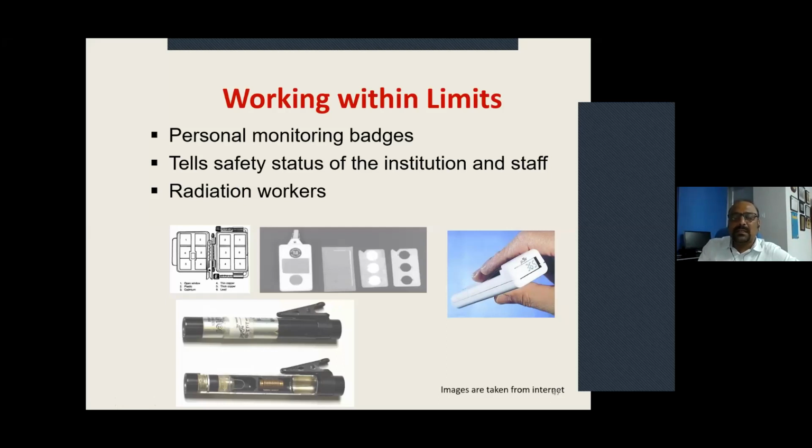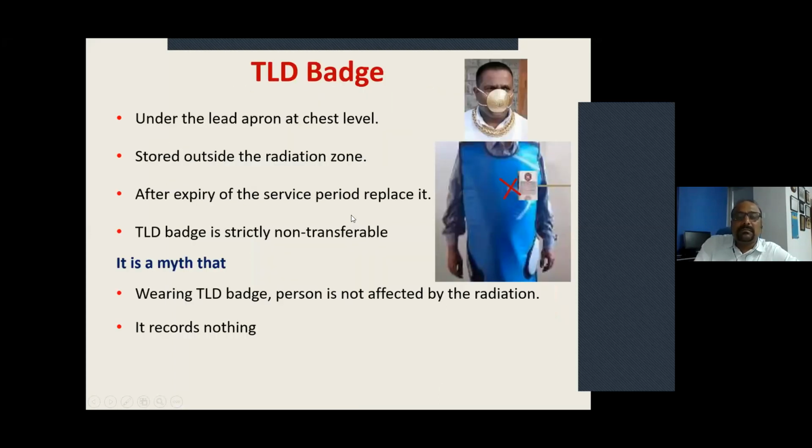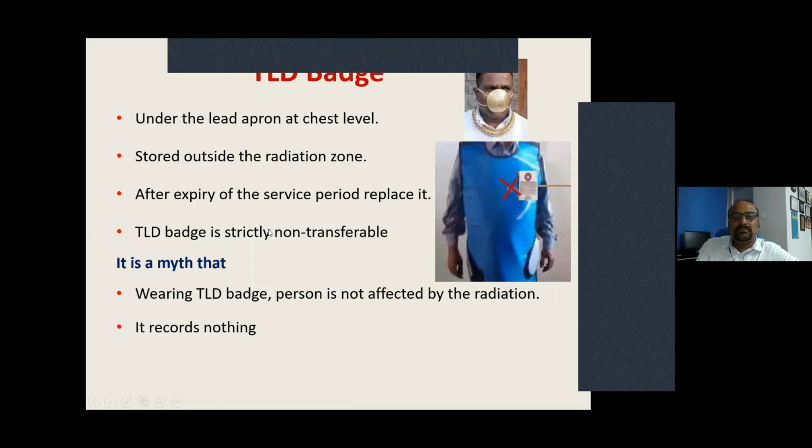It is very important, and in case of emergency, we should have a pocket dosimeter to know the radiation dose immediately, because TLD will be evaluated after 3 months. And then the TLD badge should be worn inside the lead apron, not outside. And after 3 months, it has to be replaced.